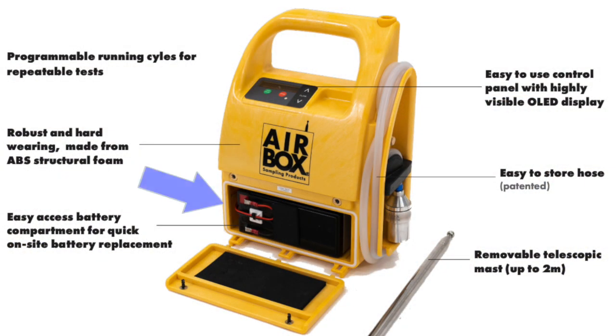The other thing we looked at is site maintenance. So this is battery operated. It can be battery and mains operated. So through a different 4 amp charger, you can run it off the mains. But what you were saying before in terms of site accessibility, not just being able to carry those pumps around but being able to work off the battery. And this is just easily accessible with a flathead screwdriver.